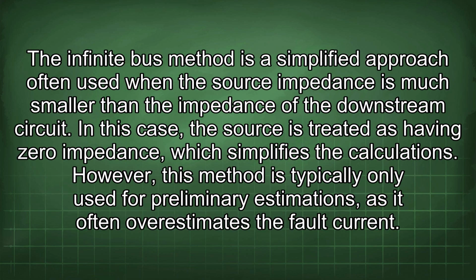The infinite bus method is a simplified approach often used when the source impedance is much smaller than the impedance of the downstream circuit. In this case, the source is treated as having zero impedance, which simplifies the calculations. However, this method is typically only used for preliminary estimations, as it often overestimates the fault current.